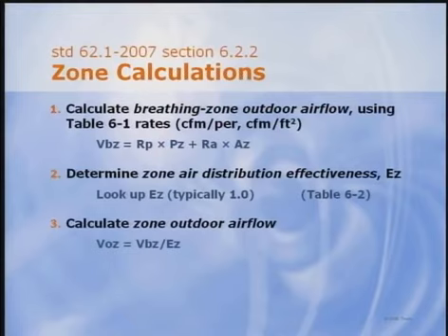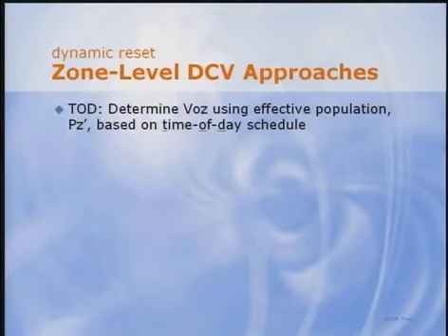This is the design value, but zones usually operate at less than peak population, so the actual outdoor airflow needed during operation can be reduced. The current zone population can be established using a variety of approaches. ASHRAE 62 lists some examples. Population can be estimated using a time-of-day schedule. This estimate might be fairly accurate in school classrooms if schedules and class sizes are predictable, but it's probably not very accurate in fast food restaurants or office conference rooms.